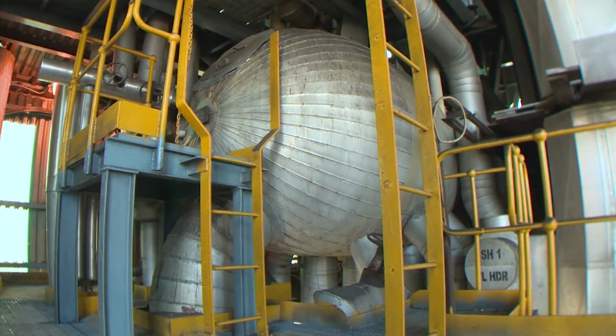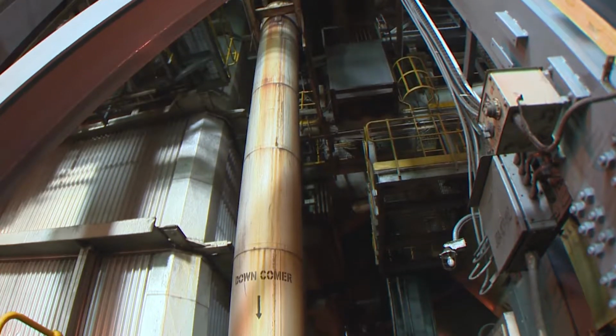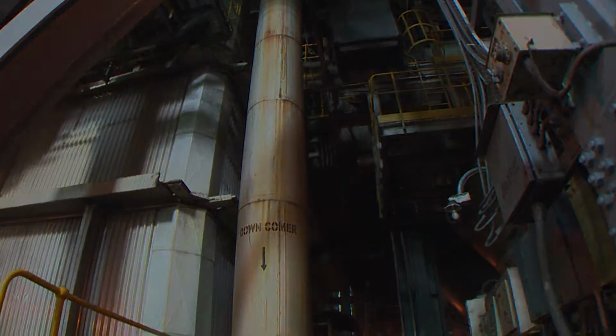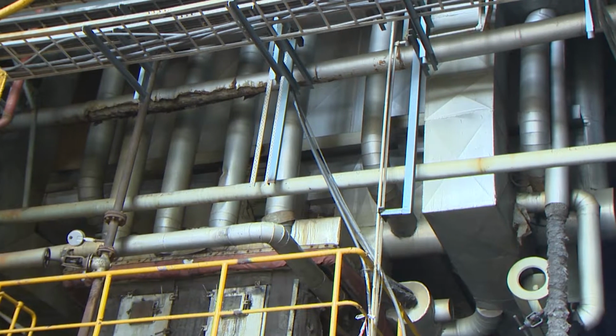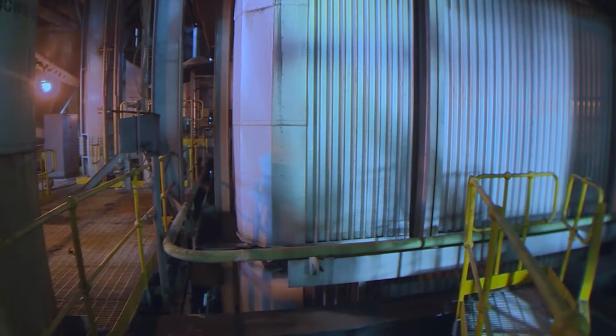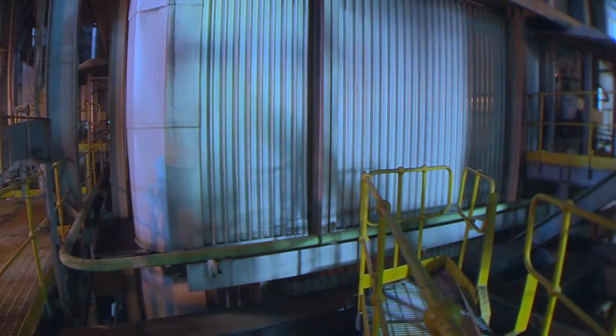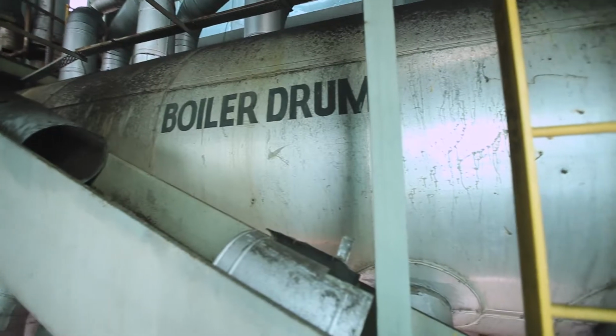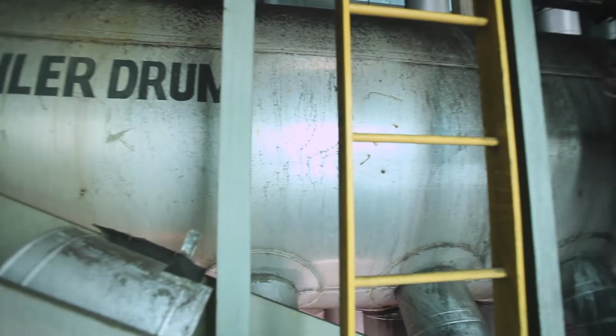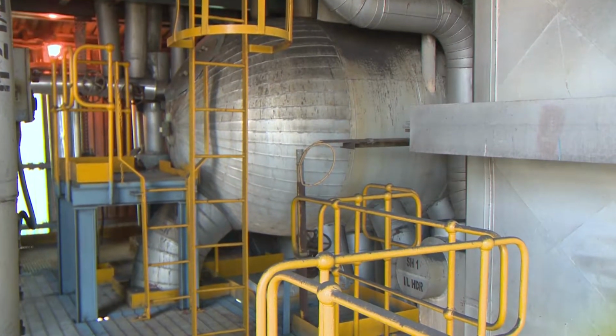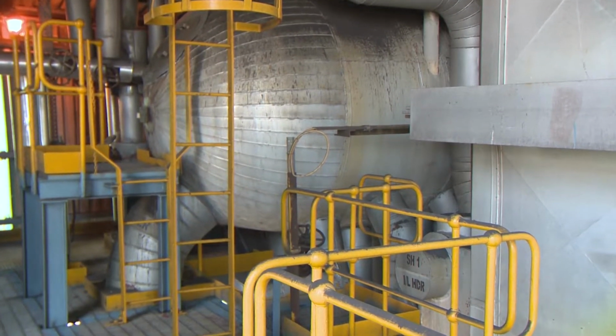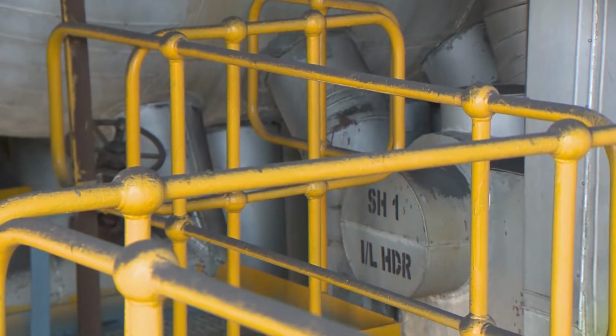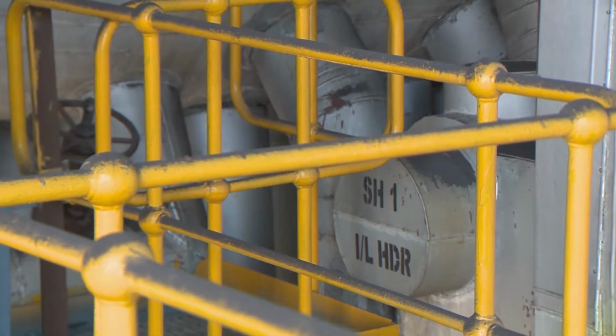Then the water from the drum flows through downcomers to the bottom header of the furnace water walls. The furnace water walls are membrane type, which absorb heat from the furnace. The steam water mixture formed in the water walls rises up naturally and enters the drum through riser tubes.